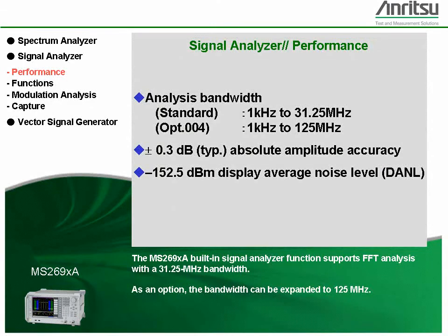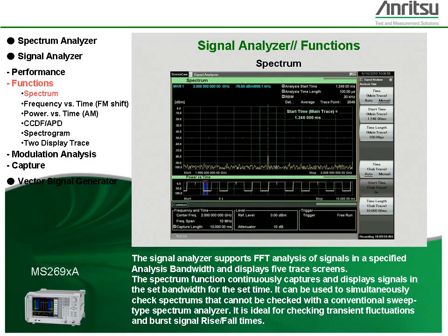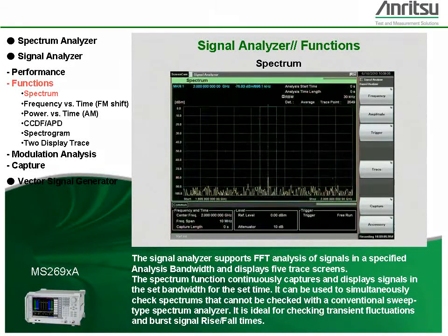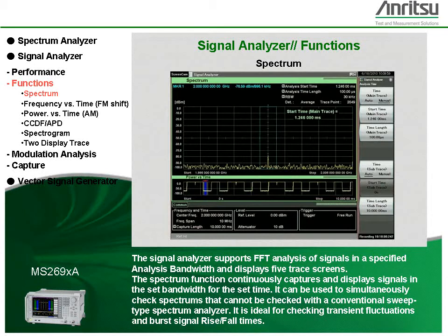The MS269XA built-in signal analyzer function supports FFT analysis with a 31.25 MHz bandwidth. As an option, the bandwidth can be expanded to 125 MHz. The signal analyzer supports FFT analysis of signals in a specified analysis bandwidth and displays five trace screens. The spectrum function continuously captures and displays signals in the set bandwidth for the set time, allowing simultaneous checking of spectrums that cannot be checked with a conventional sweep-type spectrum analyzer.